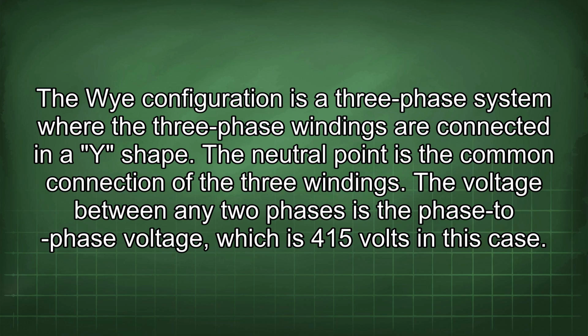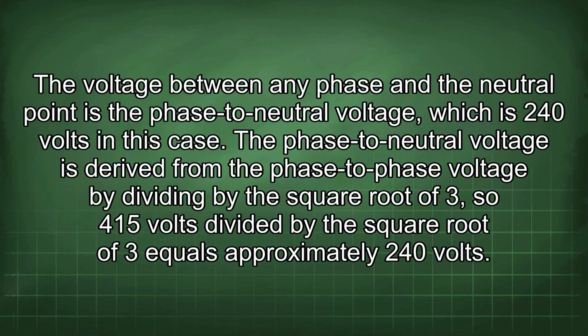The voltage between any two phases is the phase-to-phase voltage, which is 415 volts in this case. The voltage between any phase and the neutral point is the phase-to-neutral voltage, which is 240 volts in this case. The phase-to-neutral voltage is derived from the phase-to-phase voltage by dividing by the square root of 3, so 415 volts divided by the square root of 3 equals approximately 240 volts.